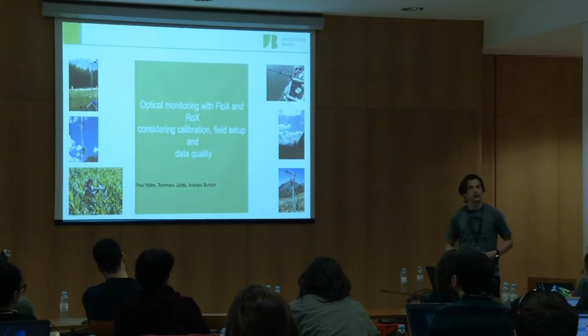And then you get raw data, which looks plotted something like this. In order to minimize the temperature drift that was already mentioned, the QE has a temperature stabilized detector chip, but we additionally also cool the detector chamber, which keeps it below a certain threshold of temperature.